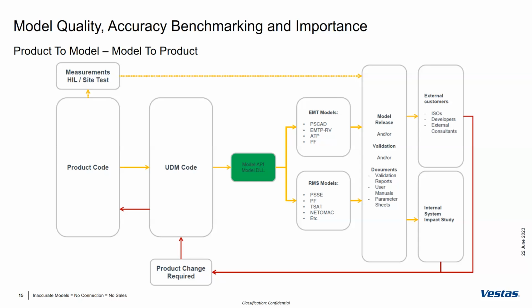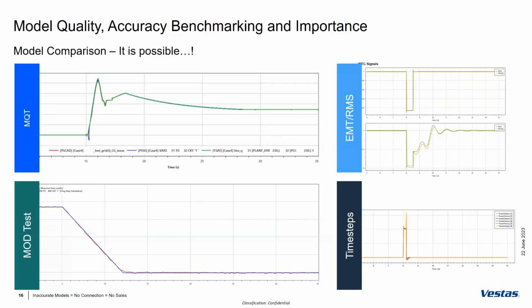Next slide. Having accurate models - and I want to emphasize it is possible, not only for Vestas, we see a lot of OEMs put a lot of effort into this - here are just a few plots. The top corner is from an ERCOT MQT, where we have PSCAD, PSS/E, and TSAT overlaid for a voltage event, low voltage ride-through. The bottom corner is a mod test for a frequency event on a site where the playback data is fed into the model and overlaid. In the top right corner, it's a different technology, comparing RMS and EMT models for low voltage events, and also different time steps, since models need to run from 1 to 10 milliseconds in RMS. Utilizing these great industry practices from NERC, CIGRE and others, we as OEMs in the industry are capable of having accurate models.